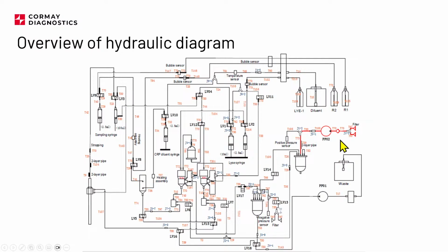This part of the circuit is similar. There is a pump, there are some filters because we are drawing air into the pump, so potentially some kind of dust can clog the pump, the same reason as here. There are some connections, couplings, reducers, Y connection, positive pressure sensor, and the chamber itself. And as I already mentioned, air bubbles can be supplied here to mix everything. During the rinsing of the outside surface of the sampling needle, we also need to make negative pressure. So this is the reason for this part of the circuit, right? Negative pressure, pump. This is it. Everything is going to the waste, right? It's removed to the waste.